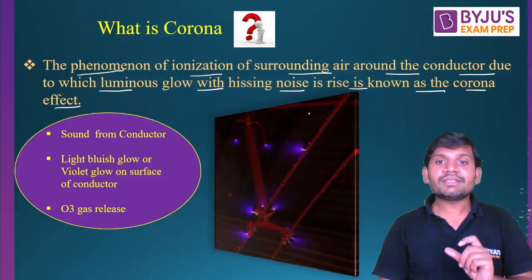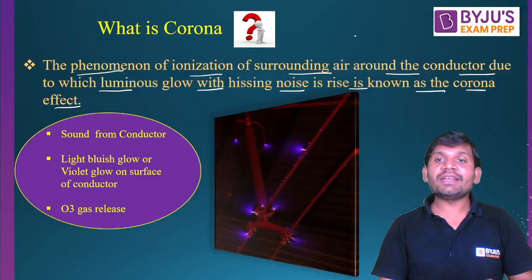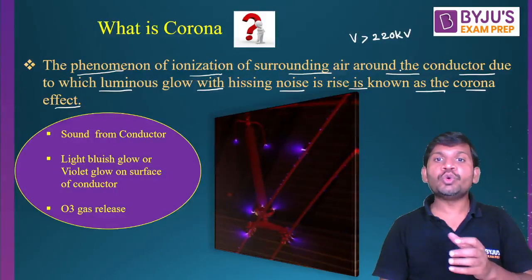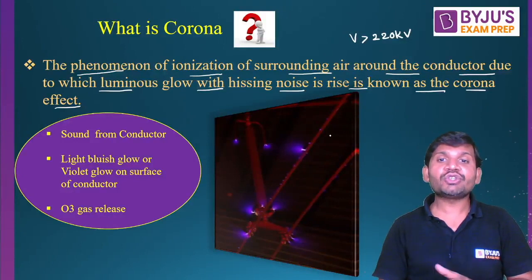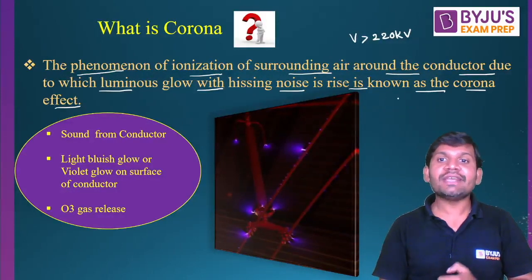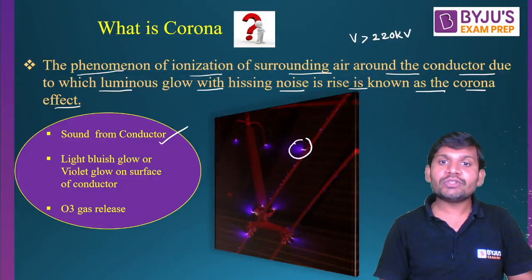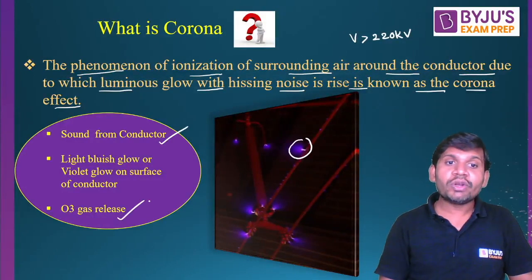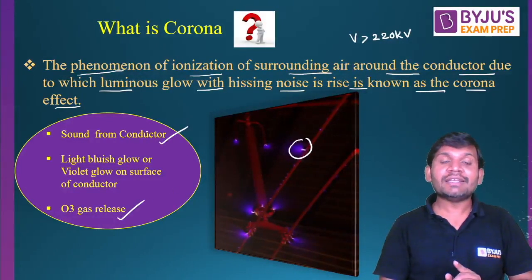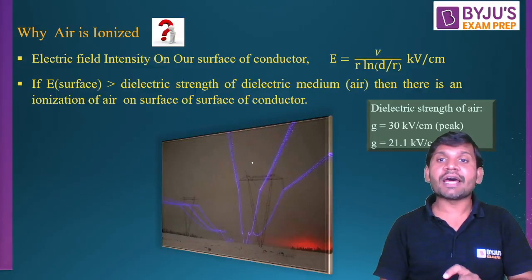Once the lines are operating at high voltages — this corona effect is more appreciable for voltages greater than 220 kV. Because of ionization of the air around the conductor, a luminous glow with hissing noise rises, and that is known as corona. Due to corona, there is a sound from the conductor, a light bluish or violet glow on the surface of the conductor, and ozone gas (O3) is also released.